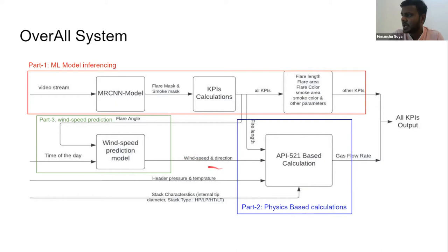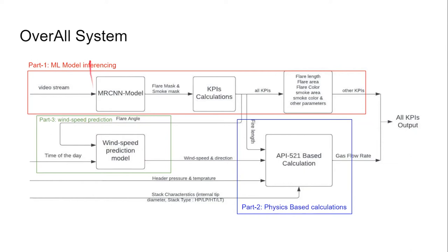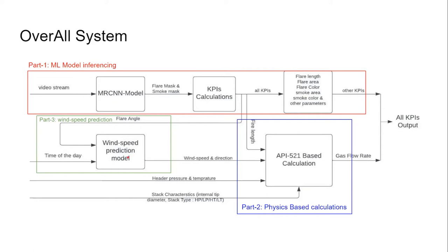Normally we would have liked to have a wind speed sensor, but at this site the client didn't want one. Since we didn't have a wind speed sensor, we looked for alternatives. We found that in the desert, wind speed was highly correlated with time of day and fairly consistent. At sunrise and sunset the winds would pick up. So we could get a typical wind speed by time of day and use a model to come up with that prediction, which worked out fairly well. If you were in central America in a jungle area, that might not work at all. For the general application, we would assume having a wind speed sensor.